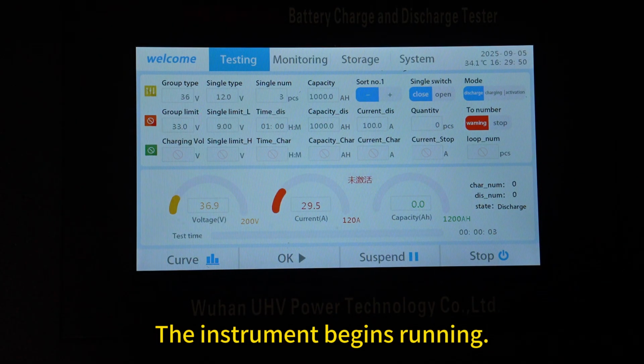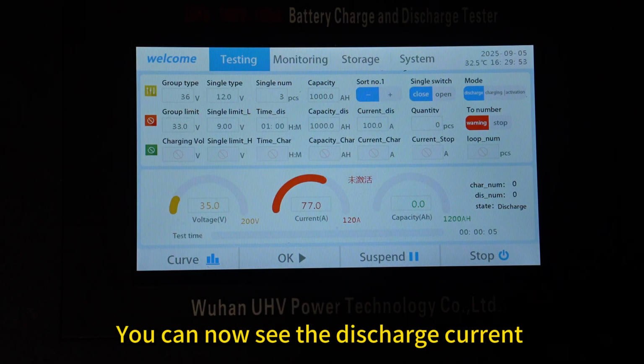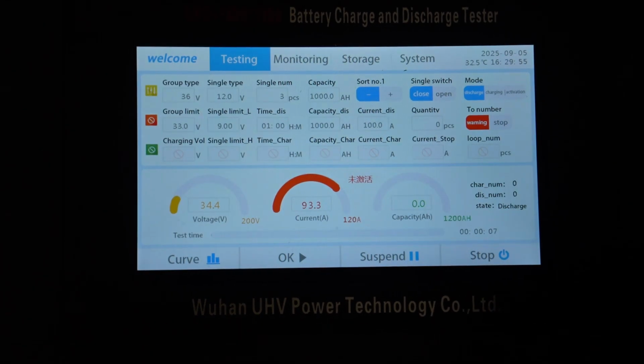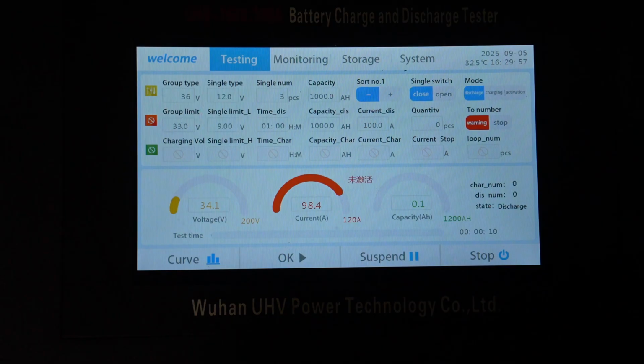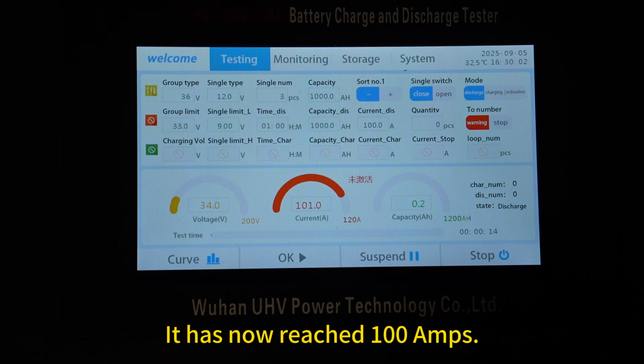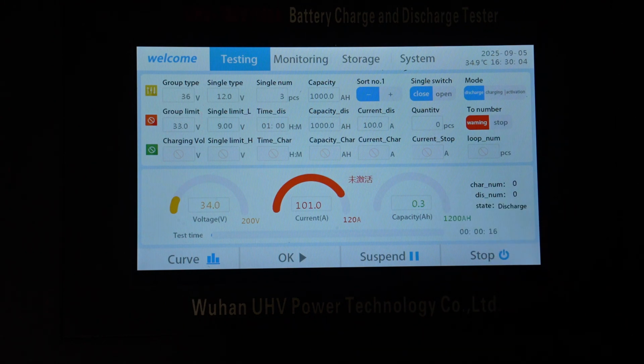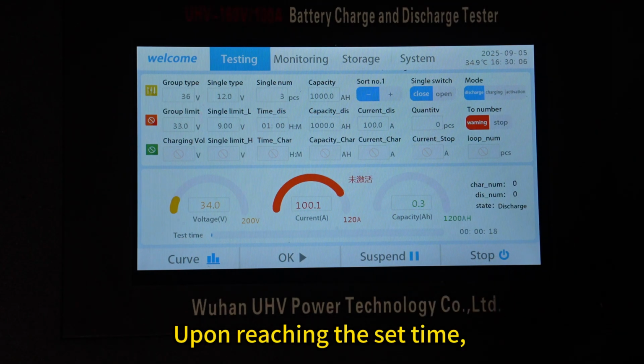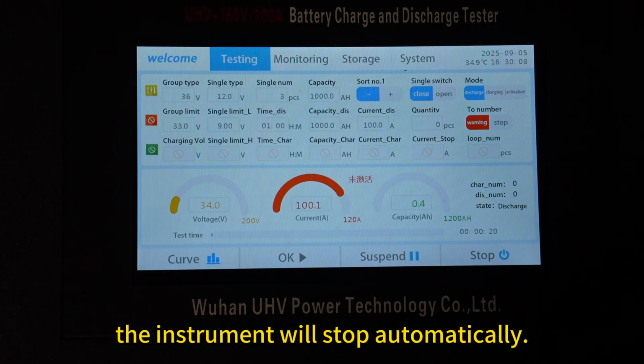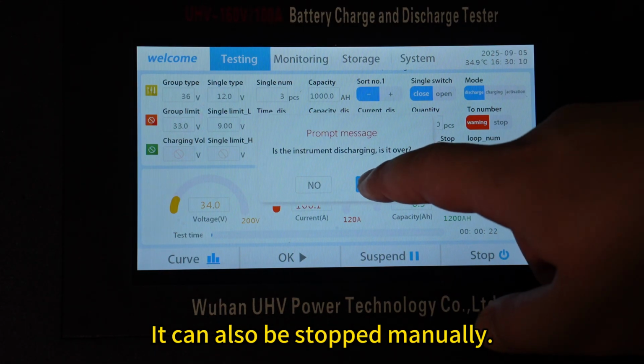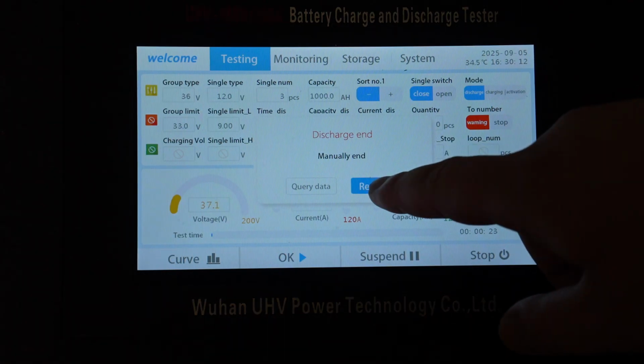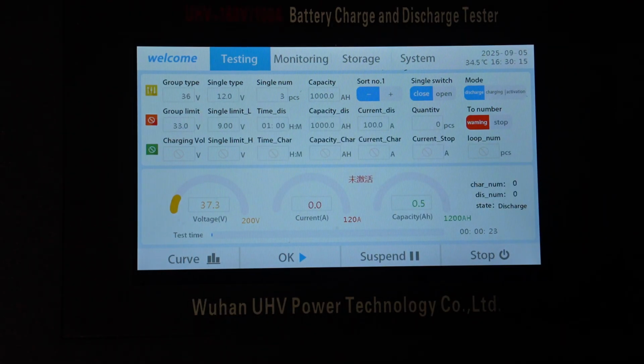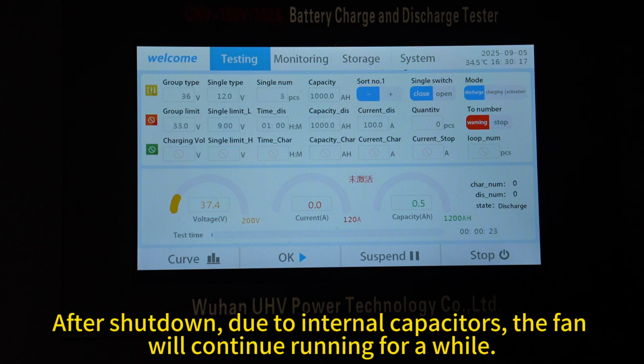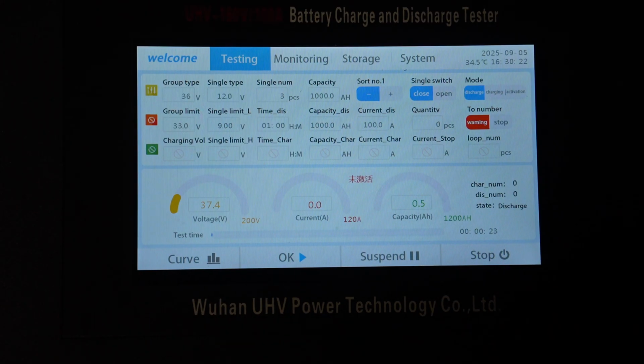The instrument begins running. You can now see the discharge current and the battery bank voltage on the left. It has now reached 100 amps. On the right is the capacity. Upon reaching the set time, the instrument will stop automatically. It can also be stopped manually. After shutdown, due to internal capacitors, the fan will continue running for a while.